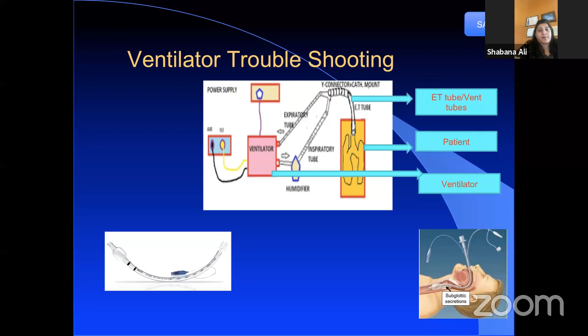So when we talk about a high pressure alarm, that means it could be because of the patient, could be from the ETT, could be pressure related. So when the patient is biting the tube, the patient has secretion all around the ETT, that's why it's alarming, or we have given too much pressure in the lungs, that's why the ventilator is alarming. Okay, low pressure alarms, every alarm which is low, that means there is some leaking going on in the ET side or on the whole circuit side, the cuff is busted, the cuff is leaking. So those are very common alarms.